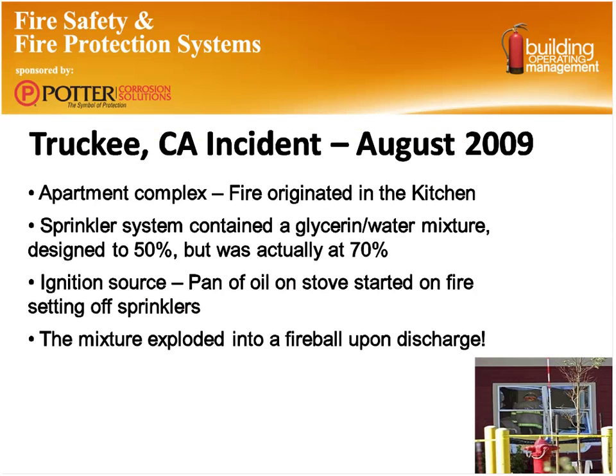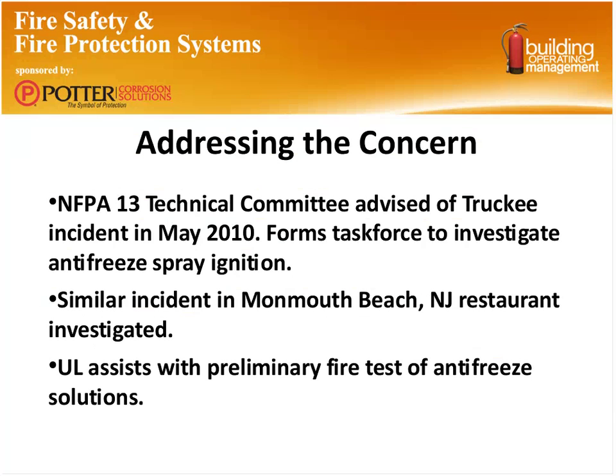So what brought this to the attention of the NFPA? Well, the issue was an apartment fire that happened in Truckee, California. In this particular incident, there was a pan fire, a very simple, small fire on a range. The fire system worked, it went off. Unfortunately, it was a freeze-protected system with a high concentration of glycerin and water. If you think about glycerin and water coming through a sprinkler system, some droplets become atomized. As that atomized mixture hit the fire front on that pan, what actually happened was a fireball and an explosion. It blew some of the windows out of this facility and caused some injuries. So the NFPA, through their committees, started to address this concern.